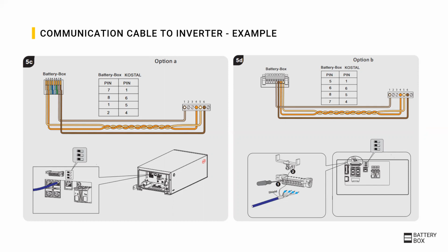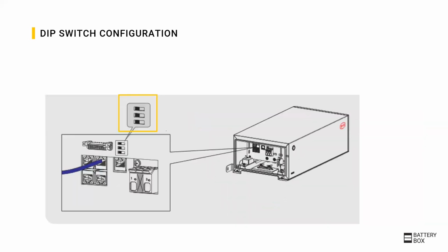If you face problems, test the cable or try another cable or try the other connection option if available for the inverter. Besides the correct cabling, also the dip switch configuration is important. Different inverters have a different dip switch setting, so please always make sure you are using the setting described in the manual. In this picture, all dip switches are on the left position, but this is different dependent on the inverter. A wrong dip switch configuration could again prevent the system from working, so please always check the correct position of the 3 switches.